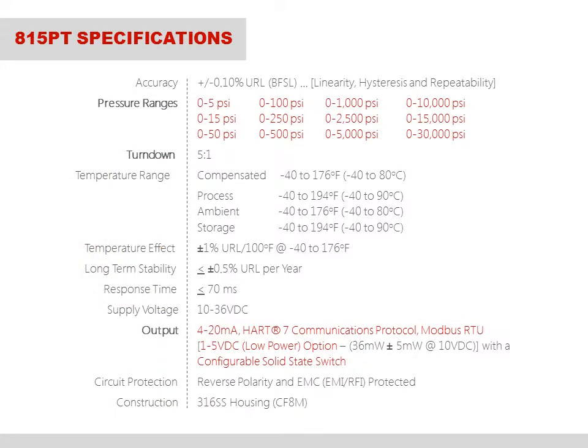Now let's take a closer look at certain specifications. The 815PT has an accuracy of plus minus 0.1% upper range limit or full scale output. It is available in 12 pressure ranges. The lowest pressure range is 0 to 5 psi and the highest is 0 to 30,000 psi. All ranges have a 5 to 1 turn down.